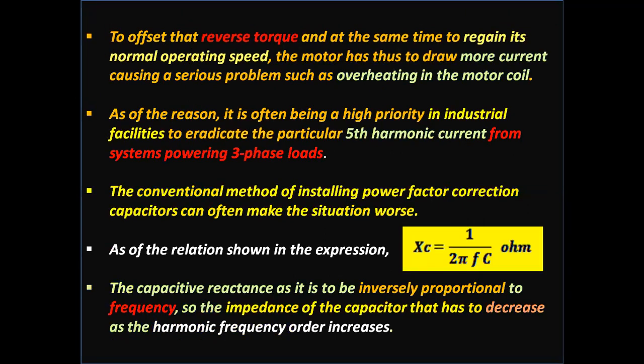To offset that reverse torque and regain normal operating speed, the motor has to draw more current, causing serious problems such as overheating in the motor coil. For this reason, it is often a high priority in industrial facilities to eradicate the fifth harmonic current from systems powering three-phase loads, because fifth harmonic current causes reverse torque.